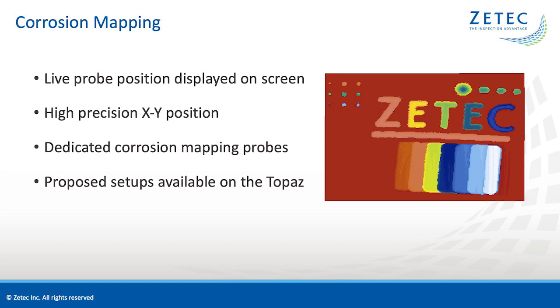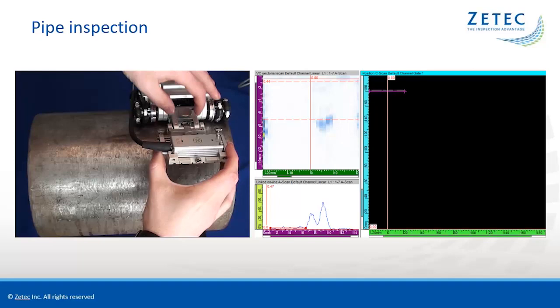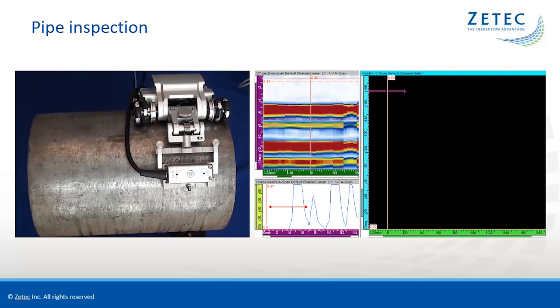The proposed setups are based on your specimen and will set up all parameters for you, still allowing you to adjust some if needed. The corrosion user case is a very common one. We use the Sweeper on an 8-inch NPS carbon steel pipe with the probe oriented for circumferential scanning. The pipe is 0.39 inch thick and has simulated natural corrosion and pitting. At the start, the probe is lifted and the brake is engaged so the scanner does not fall off the pipe. The user simply unlatches the probe holder to release the spring-loaded mechanism, then disengages the brake and starts scanning.